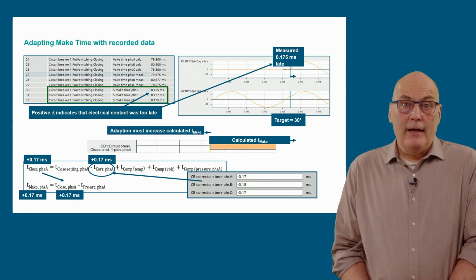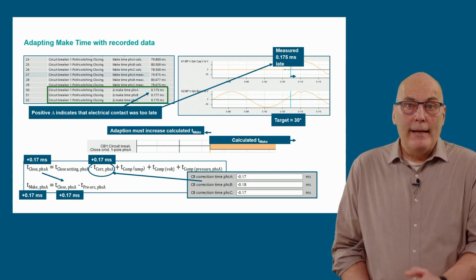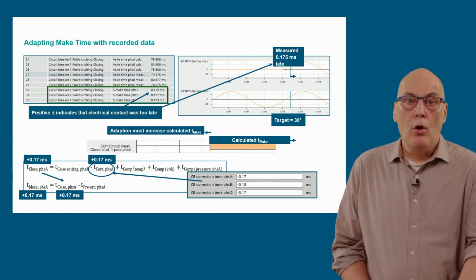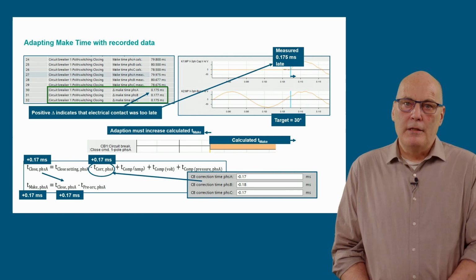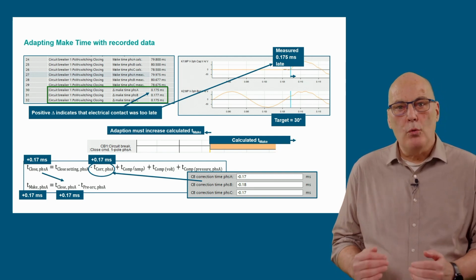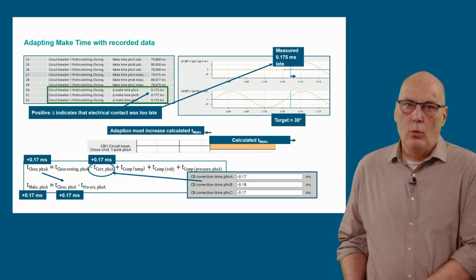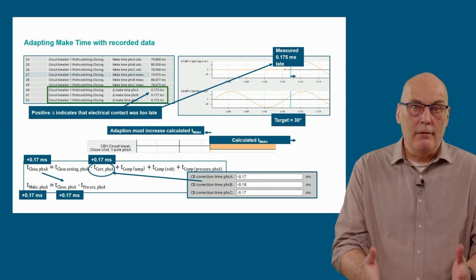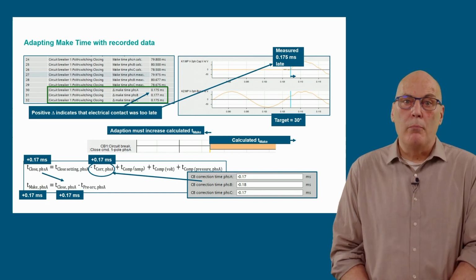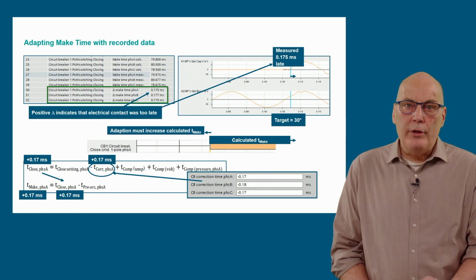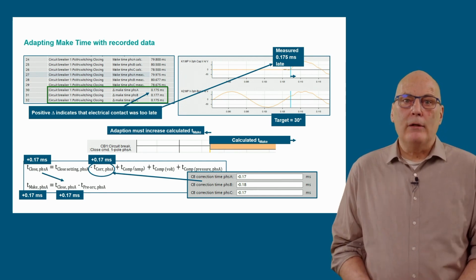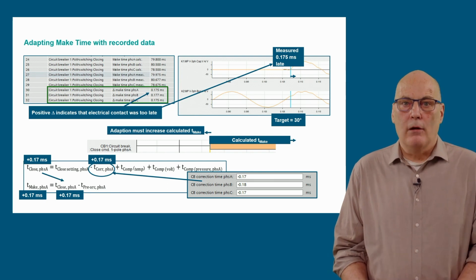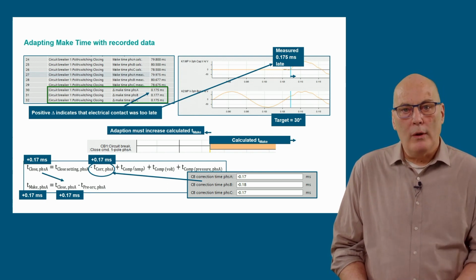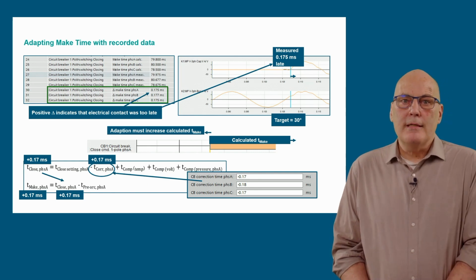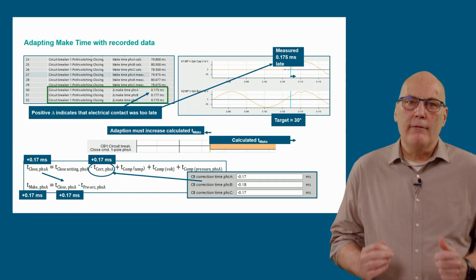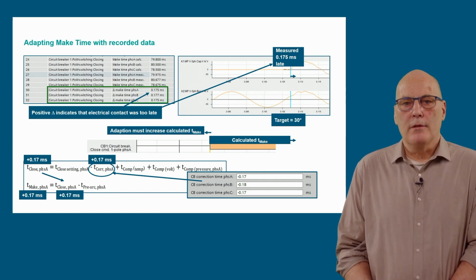As the correction factor has a negative sign in the equation, a negative setting must be applied to obtain a longer calculated closing time. In this example, set the correction time for phase A to minus 0.17 milliseconds in order to increase the calculated closing time by 0.17 milliseconds, as shown in the blue values. The increased calculated closing time will automatically increase the calculated make time, so that the next close with these settings will be issued 0.17 milliseconds earlier. This is the only parameter that should be changed to compensate for observed delta make times during service.